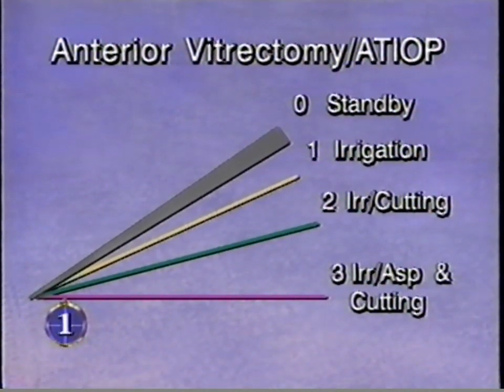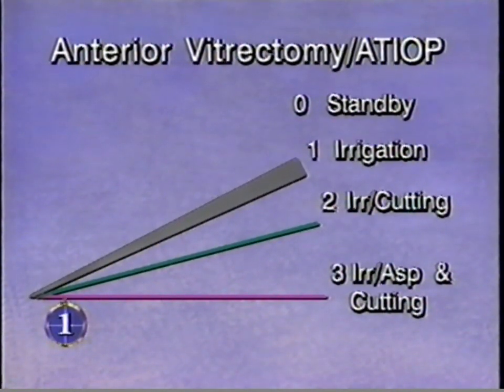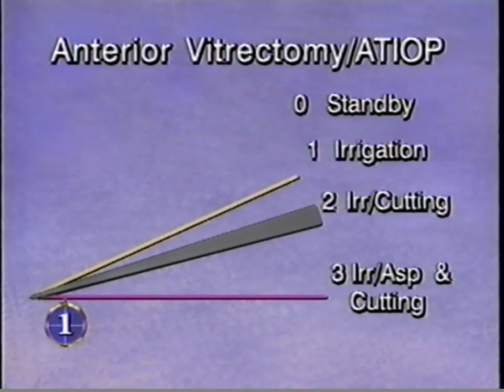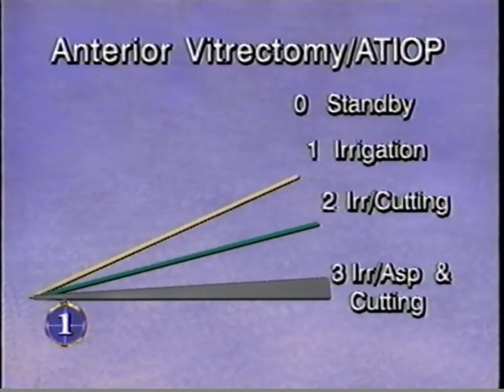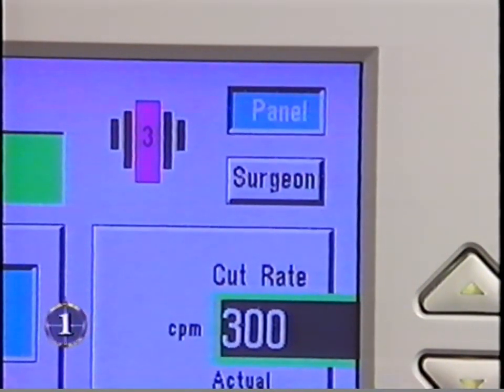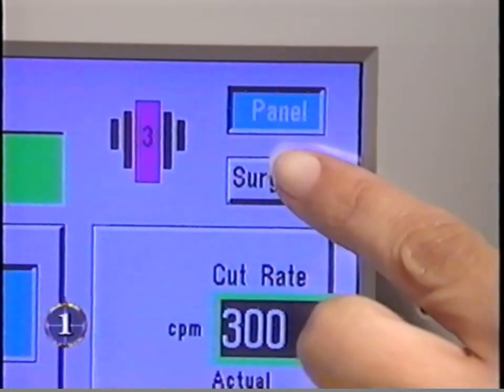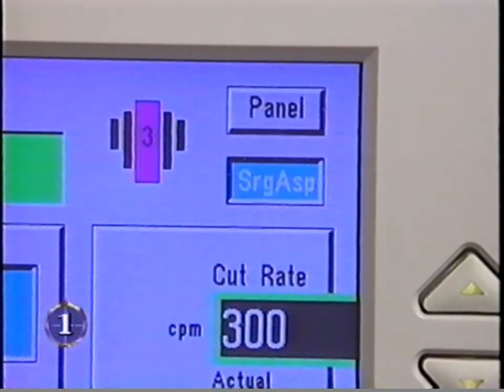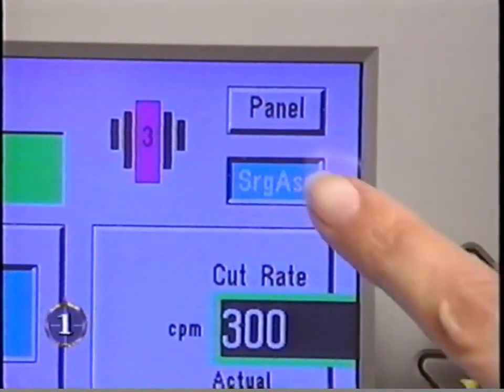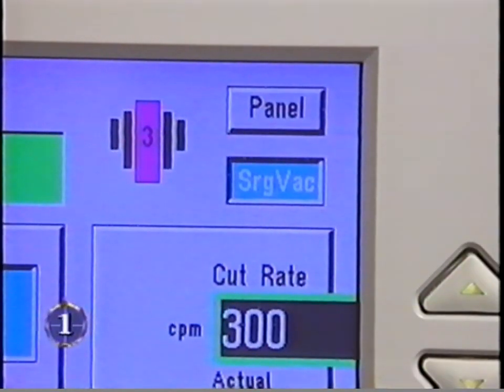The 2 submodes of the vitrectomy mode also vary between panel and surgeon control, with aspiration and vacuum parameters. In the VIT ATIOP submode, position 1 is irrigation, position 2 is irrigation and cutting, and position 3 is irrigation aspiration cutting. Under panel control, position 3 is irrigation aspiration cutting. With surgeon asp control, position 3 is irrigation and cutting with linear aspiration rates and fixed vacuum level. With surgeon control of the vac parameters, position 3 is irrigation and cutting with linear vacuum levels and fixed aspiration rate.